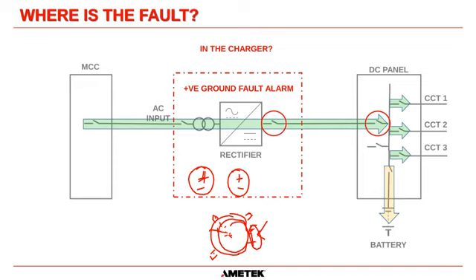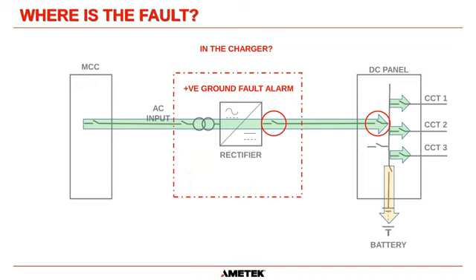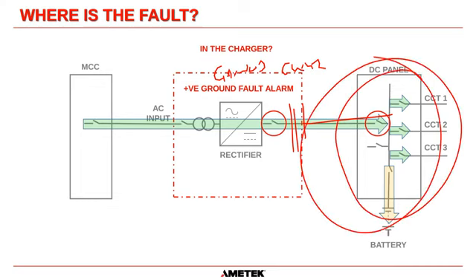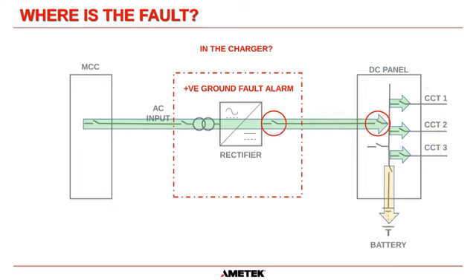Okay, so that is really the only time. The only time that you will ever see a ground fault in a charger is usually either down to a wiring issue or down to capacitors that have had the insulation broken down because somebody has installed them incorrectly. Now obviously, if you do open this DC output breaker and the ground fault clears inside the charger, then we know that the ground fault is somewhere out here, because the ground fault in the system is cleared.